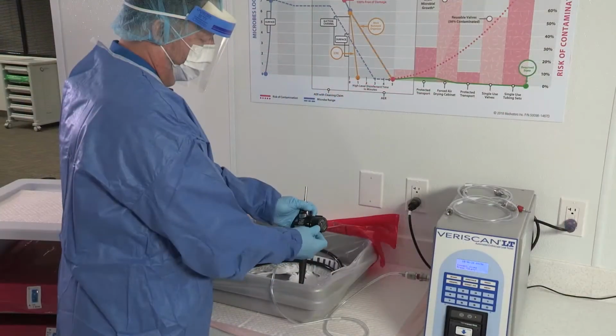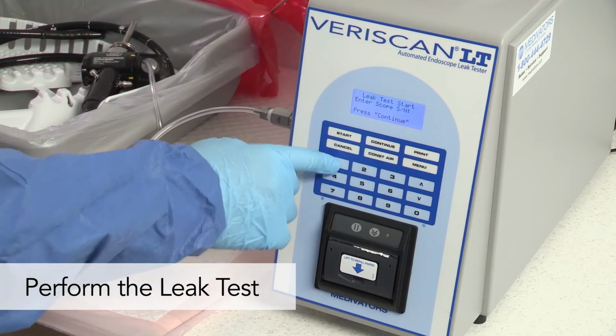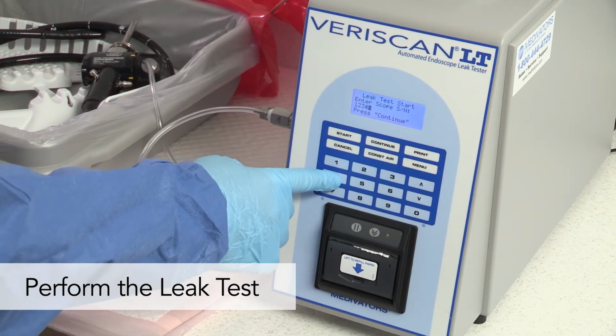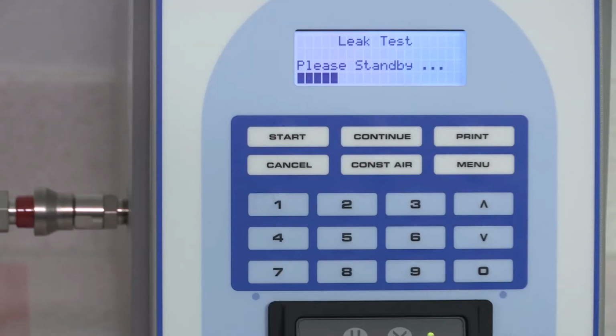This may be performed as a dry leak test with the Veriscan leak tester. Although the DSD EDGE Reprocessor has a leak test feature, it does not replace the leak test that is required by the endoscope manufacturer's IFU.